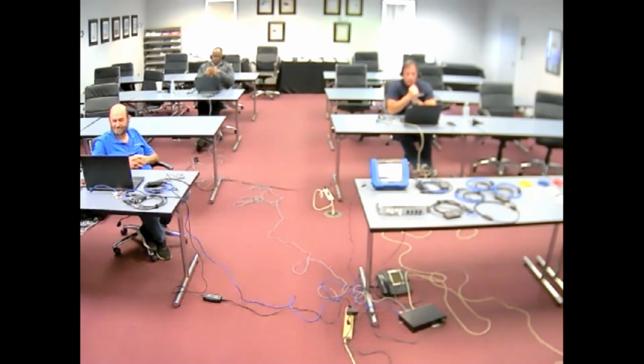Jay also asked, can you use any IP number? The answer is absolutely no. It has to be an IP address that's valid for the network you're configured on. As an example, if I'm going to plug into my local network, I have to know what the valid IP address is for that network. If you're unfamiliar with that, speak to your IT person or contact Ken, Thurman, or myself in tech support. These are not Dranetz rules, these are networking rules with the IP stacks. There are certain ranges of addresses that are valid, not just to enter into an IP network, but that will function on your network.